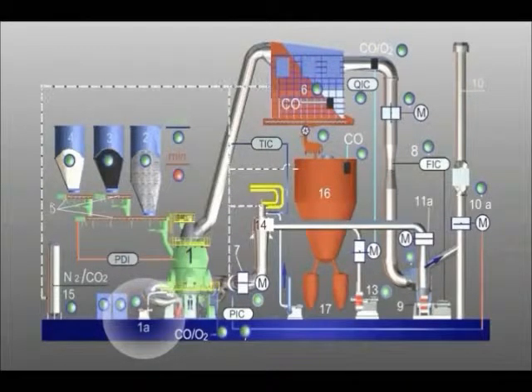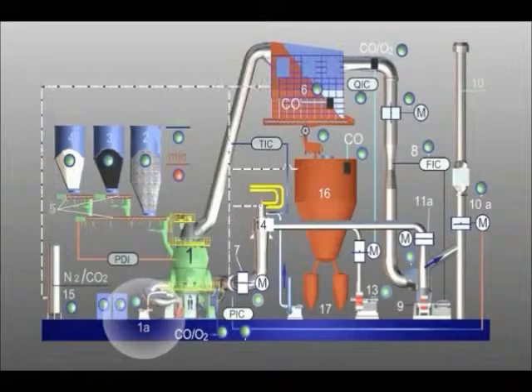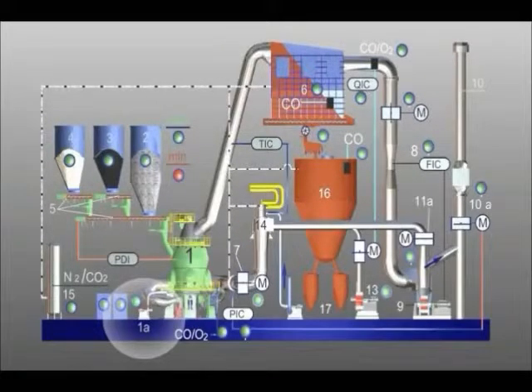The seal air fan at position 1a is switched on. The sealing air at the grinding table seal, the grinding rollers, and the classifier drive is needed in order to prevent dust from accumulating in the bearings.